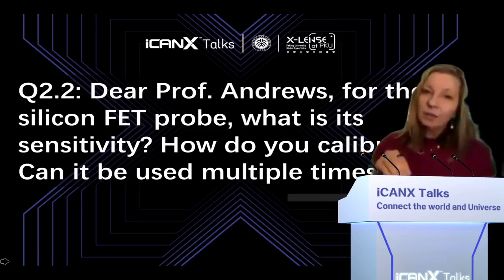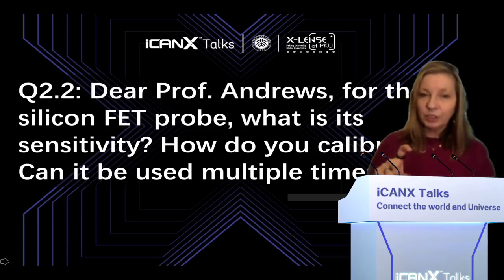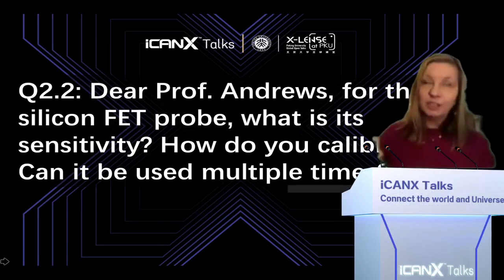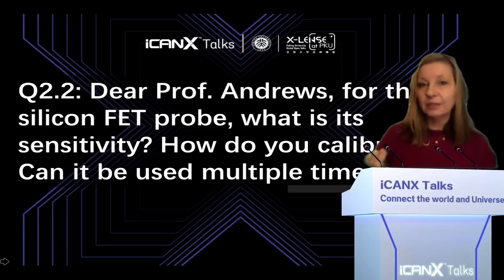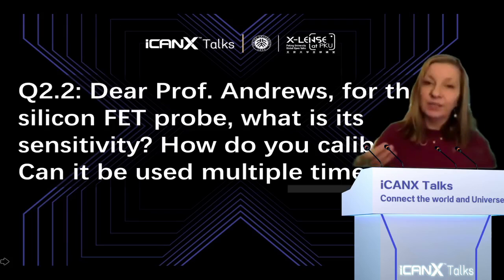We calibrate those sensors. We typically calibrate them before we do measurements. In other types of measurement devices that we use, we would also calibrate the sensor after we make the measurements. And it turns out that those calibrations after the measurements are more important because at that point, the sensor has been exposed to tissue and the response is more like what we would expect to find in the brain.